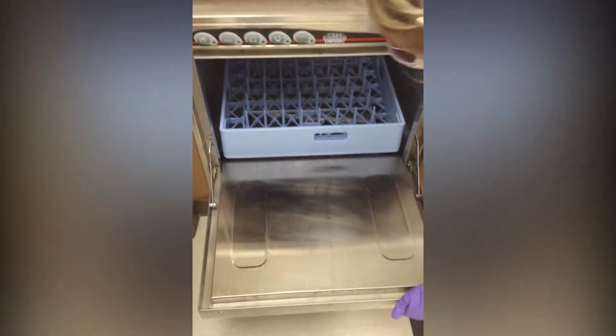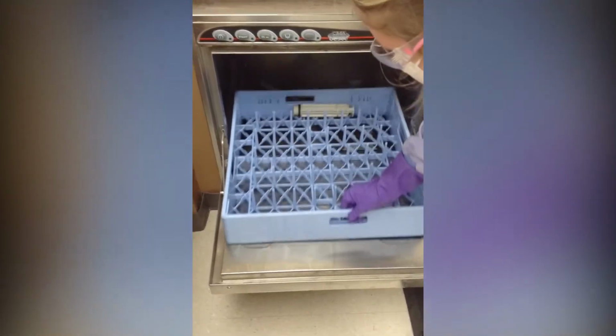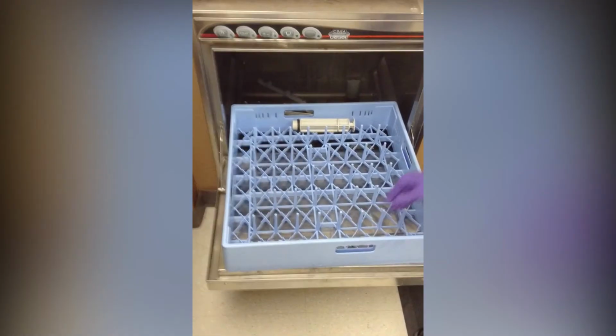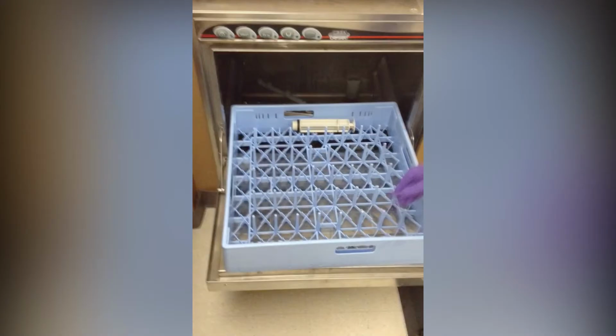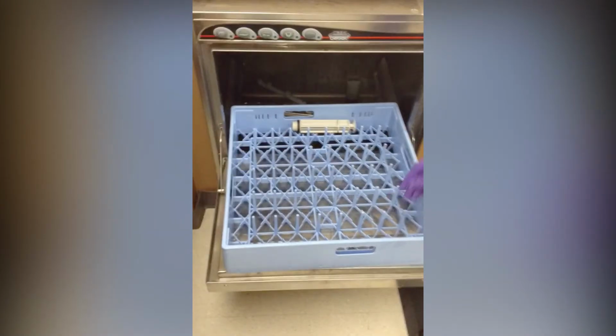And at the end of day procedures, make sure the instrument washer is drained. Put on heavy utility gloves, pull the plug out of the drain, turn it off, press and hold the drain button. When you hear the swoosh sound, the draining is complete, and leave the door open to dry overnight.